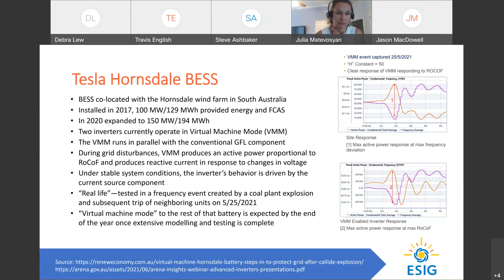So they actually real life tested this project when a nearby coal plant tripped at the end of May this year. And so what you can see on the right hand side here, the top graph shows the response of the entire battery plant. So the plant has 2 inverters that are in grid forming mode, and then everything else is grid following. And overall response of the plant looks like a frequency response, governor-like response, if you will. But then if you look at the bottom chart, you can see response of these 2 inverters that were in virtual machine mode, as Tesla calls it. And so you can see that response more reminds you of inertial response from synchronous generation, because it's coincidental with the frequency decline. So it's at the same time, and it peaks even before the frequency nadir. Next slide, please.